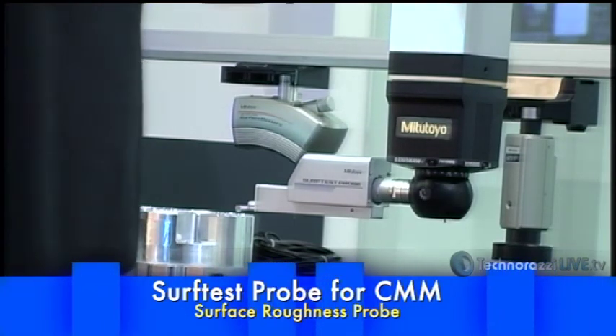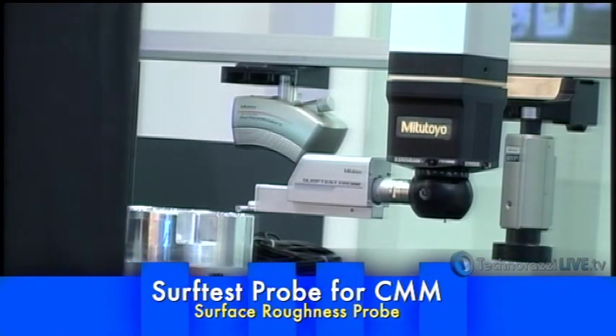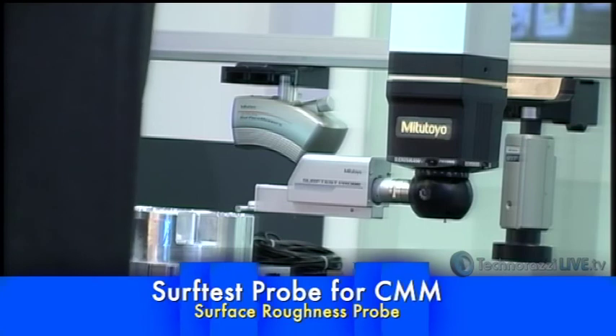You've got a surf test probe, right? Essentially, we've taken our most successful portable surface unit, the SJ210, and we've integrated it with our Crysta-Apex CNC CMM. In conjunction with a PH10M probe system and rack from Renishaw, we've mounted it into it. So when deployed, the probe will go over the measurement area, it'll lower itself, and a diamond stylus makes a trace across the part and begins to take a reading.